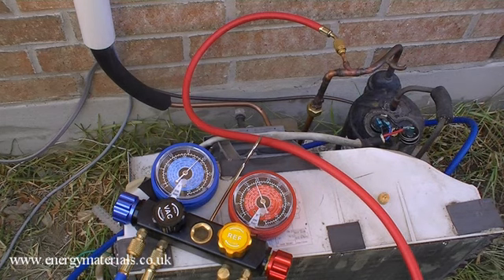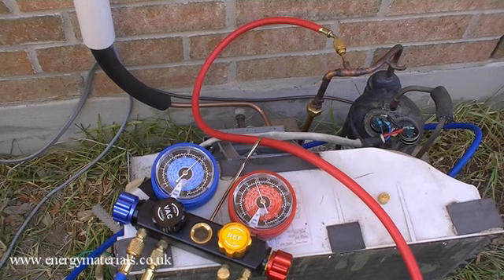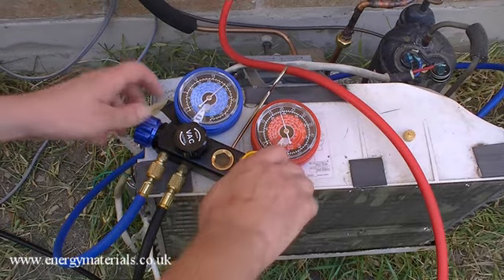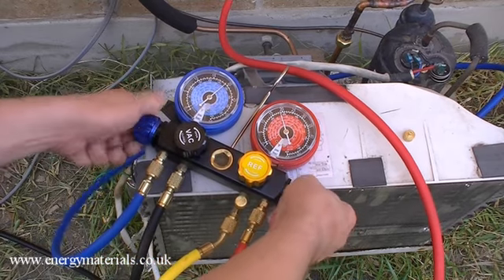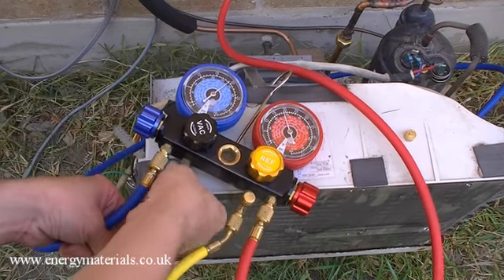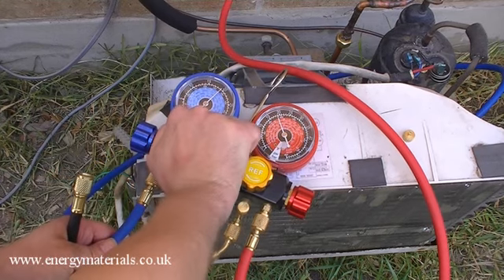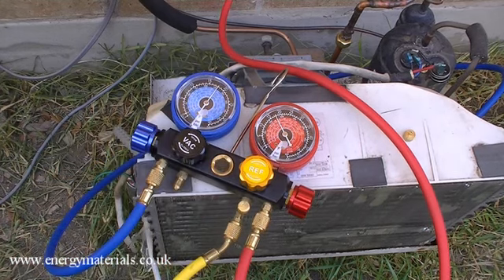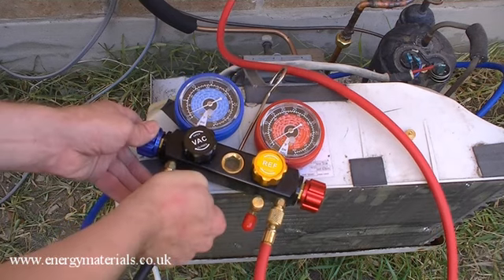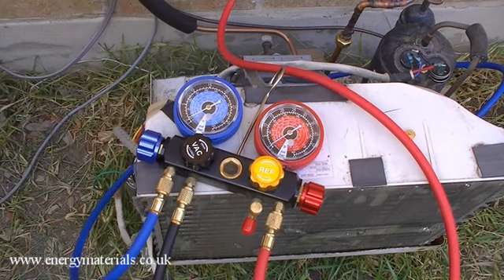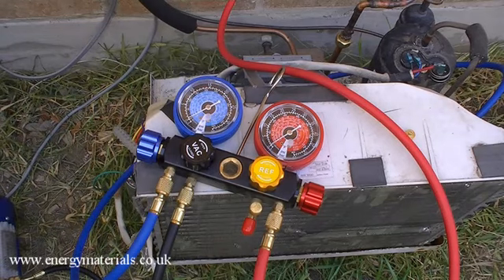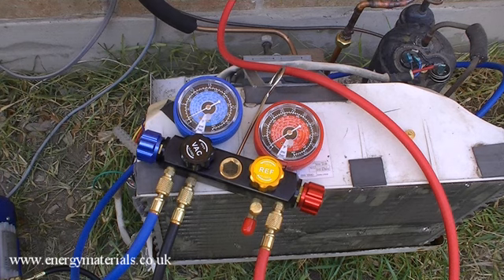So we maintained a pressure of 300 psi or around 20 bar in the high pressure side, low pressure side, which is all connected. So the system integrity is good. So we're now going to release the nitrogen gas that we're containing within our line set. To do this, we undo a fitting and release. So now connect our vacuum pump and evacuate the line set to remove any air, nitrogen, moisture from the line set. And begin the process of evacuating the line set.